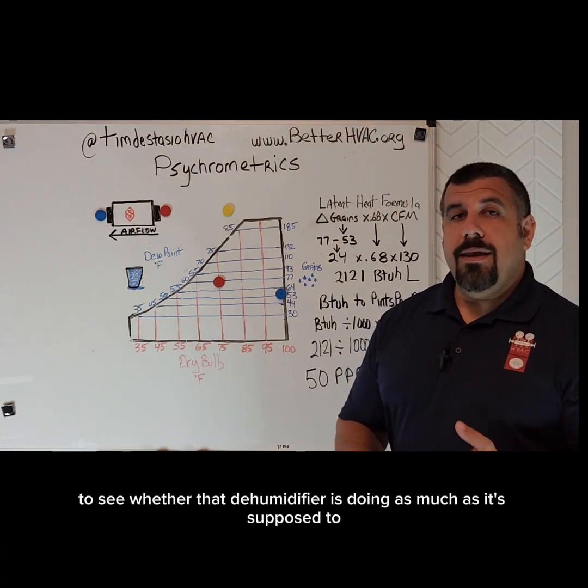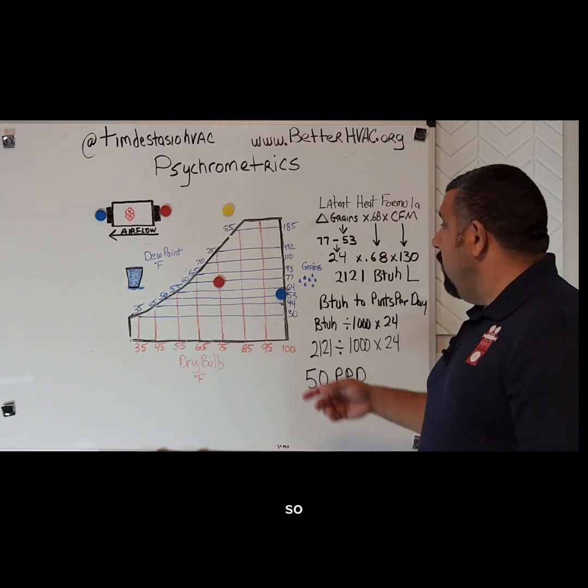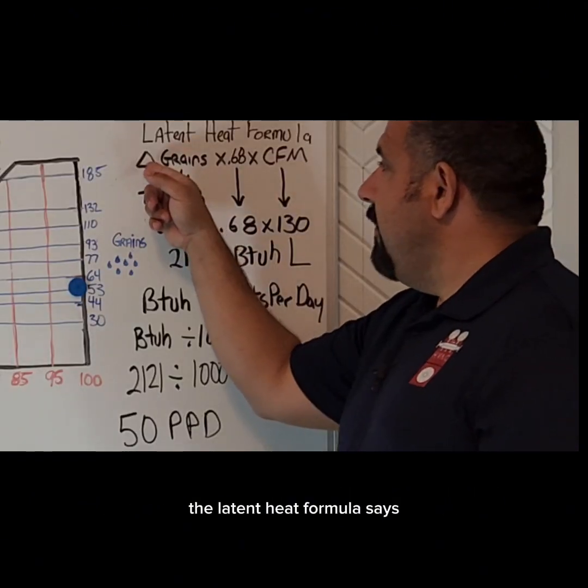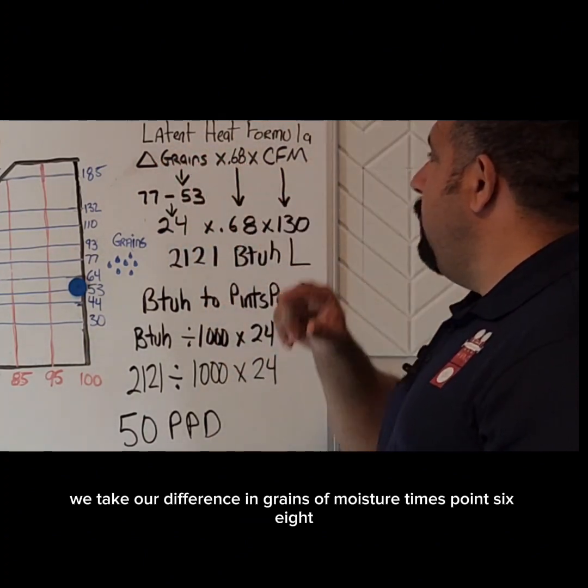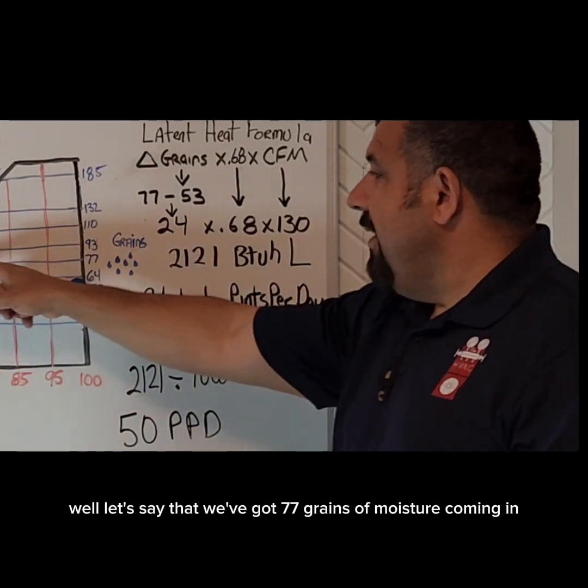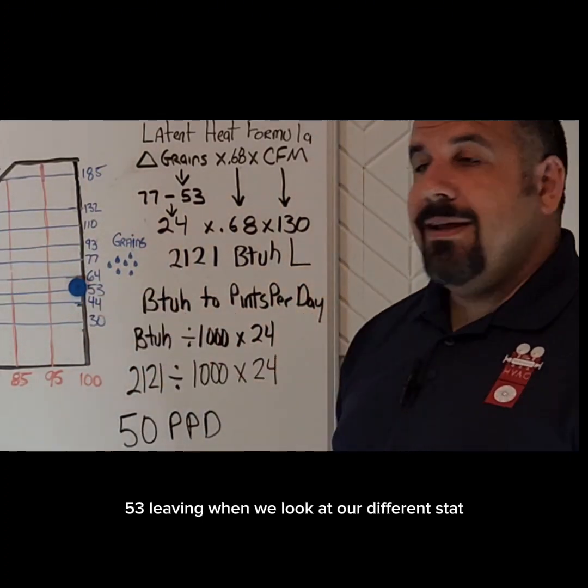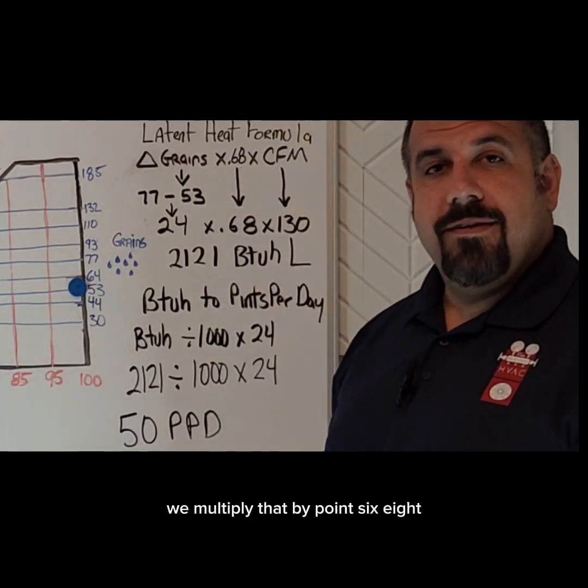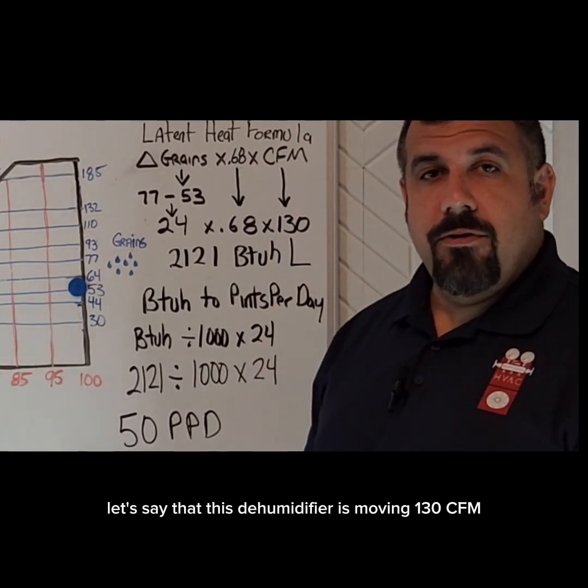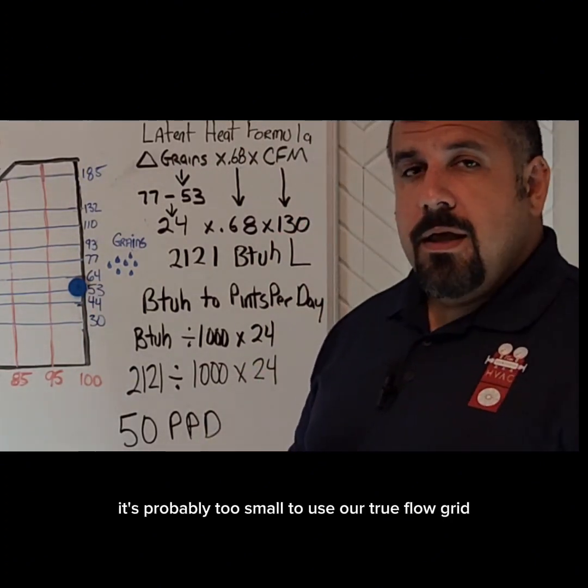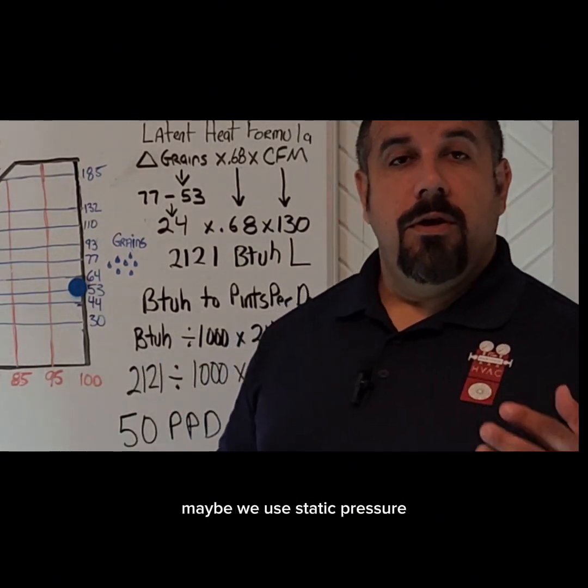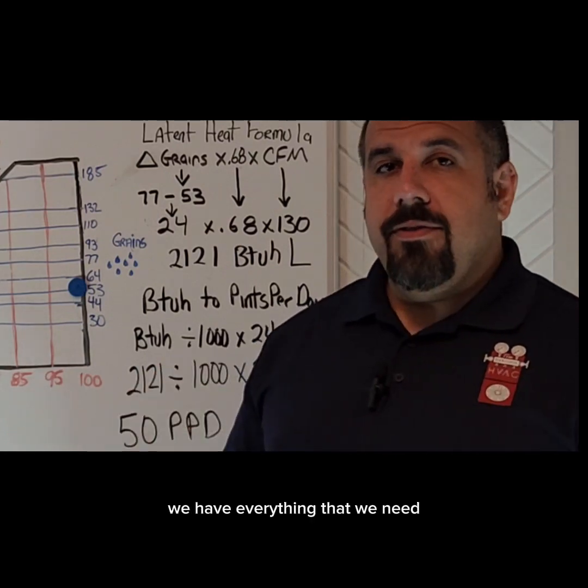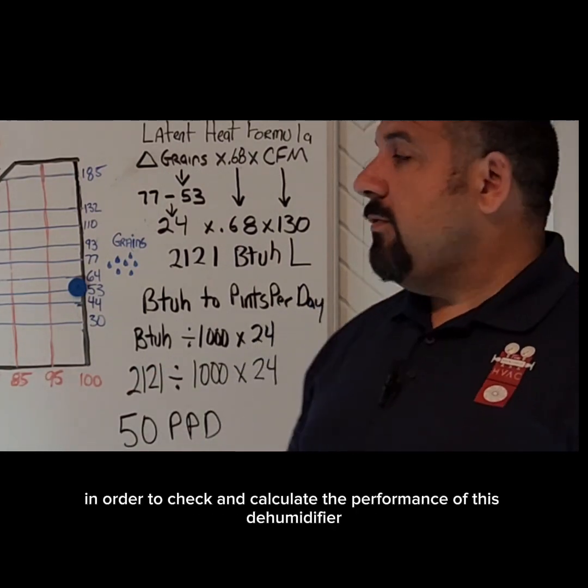Let's actually calculate to see whether that dehumidifier is doing as much as it's supposed to. We've got to figure out what our difference in grains of moisture is, because we're going to use the latent heat formula. The latent heat formula says we take our difference in grains of moisture times 0.68 times our CFM. We've got 77 grains of moisture coming in and 53 leaving — that's a 24 grain difference. We multiply that by 0.68. Let's say this dehumidifier is moving 130 CFM. We're going to need to measure that somehow — it's probably too small to use our true flow grid; maybe we use static pressure and check it against the manufacturer's information. Either way, let's say we read 130 CFM. We have everything we need to calculate the performance of this dehumidifier.